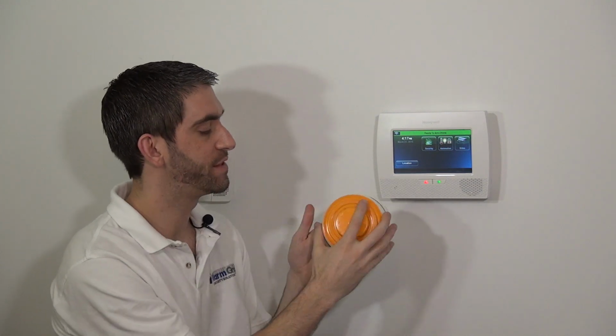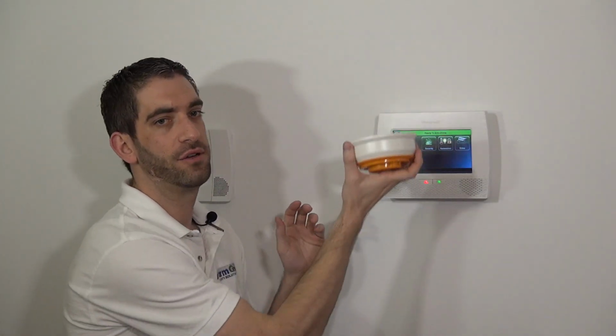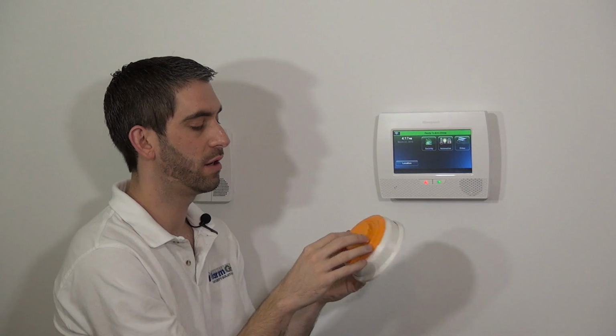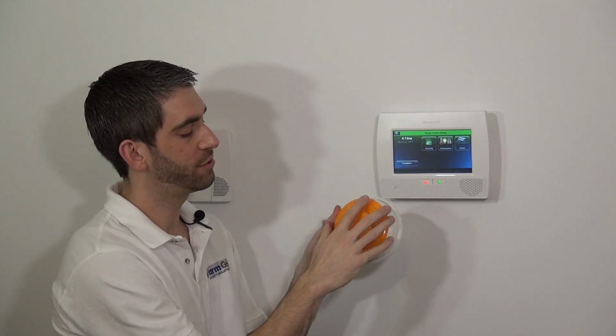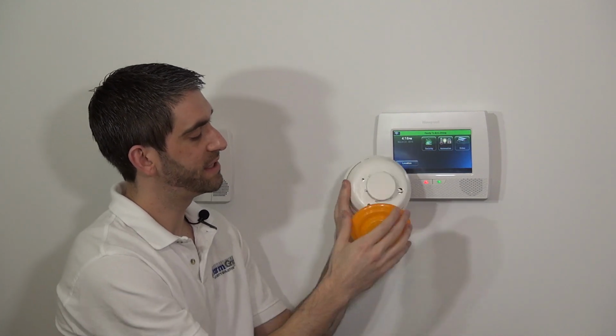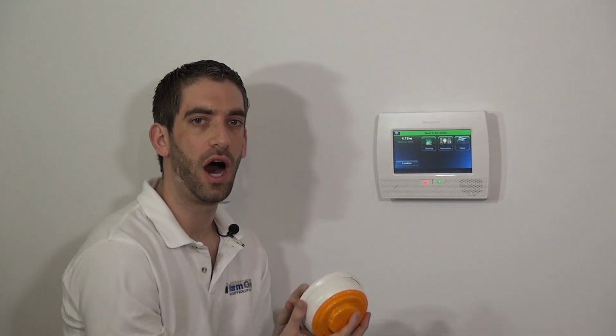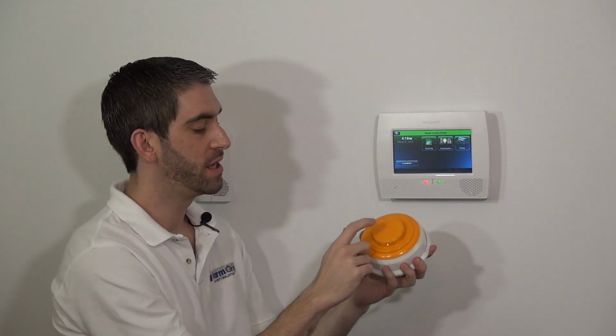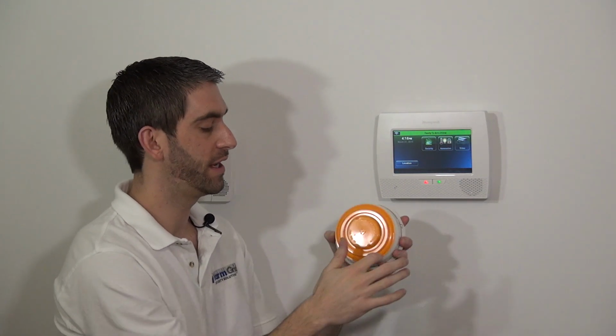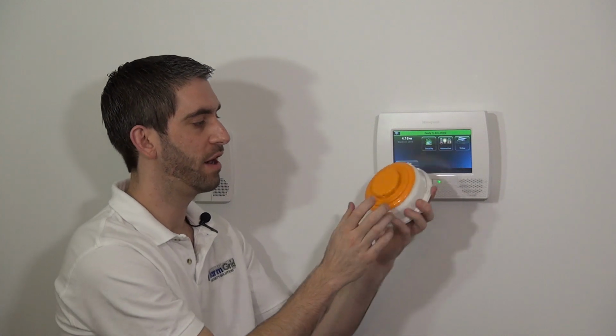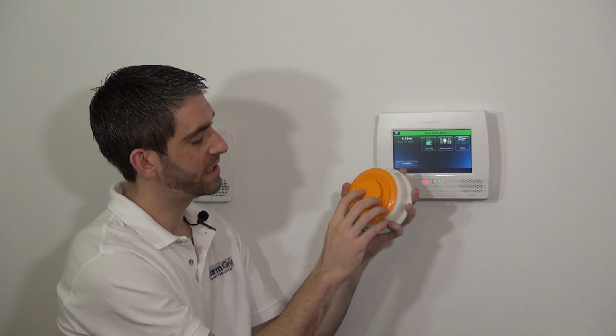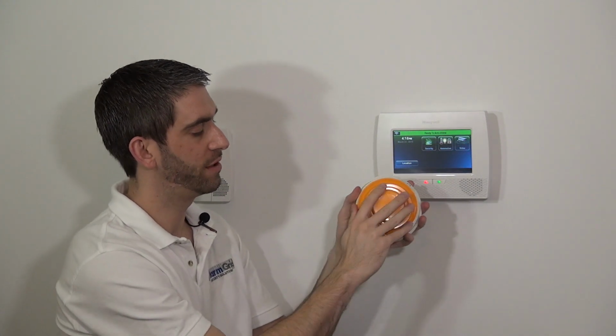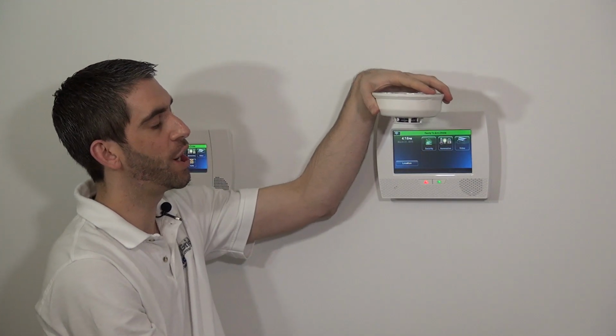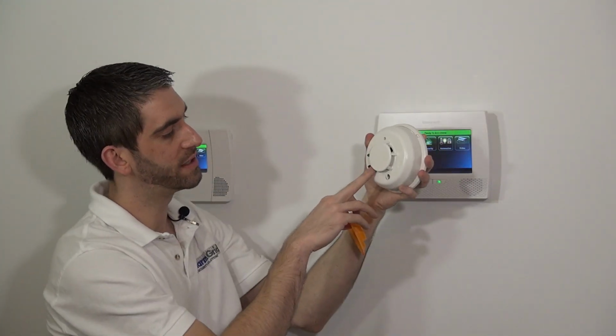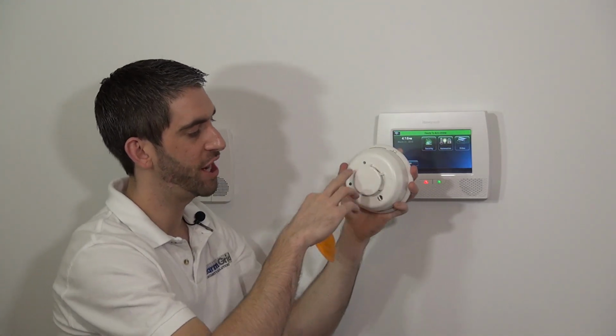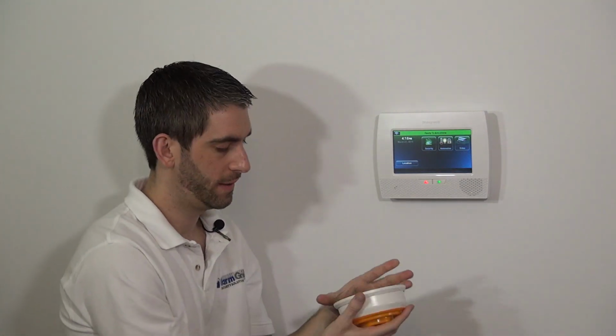If it's pre-construction and you want to mount your sensors but you know that there's going to be work going on in the home, no dust or debris would be able to get up into this chamber, which would throw the sensor off and hurt the sensitivity of the sensor. So if you're in your installation phase, you should keep the cover on. It even says right on here, remove before operation. Once you have it installed and you're ready to go, you pop the cover off so you can see your LED indications and you have your chamber ready to detect smoke.